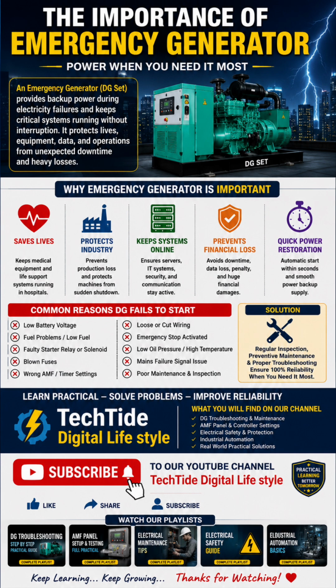In hospitals, it can save lives by powering medical equipment. In industries, it protects machines and production lines. And in offices or data centers, it keeps servers, security systems, and communication equipment active. But many times, generators fail to start during emergencies because of small issues like low battery voltage, fuel problems, faulty relays, blown fuses, wrong AMF settings, or wiring faults.